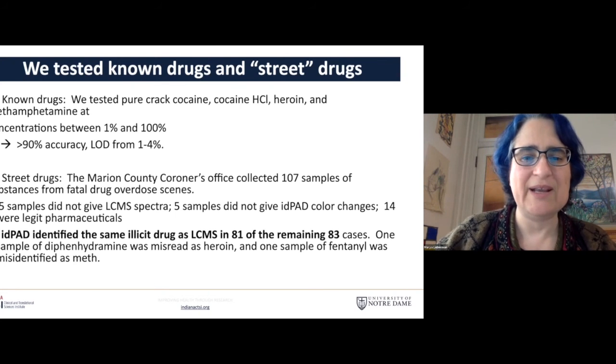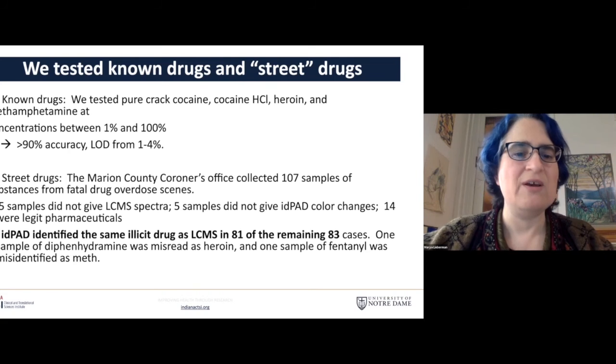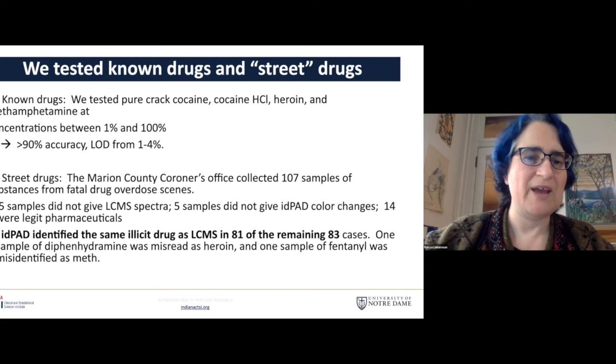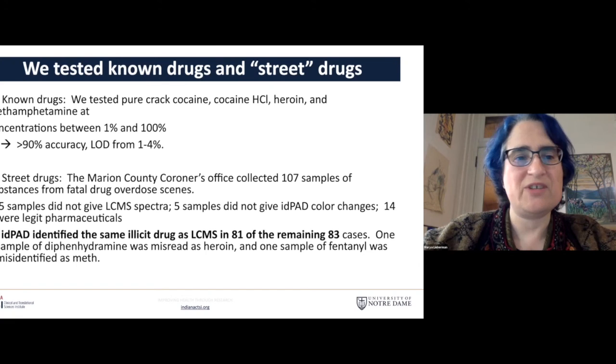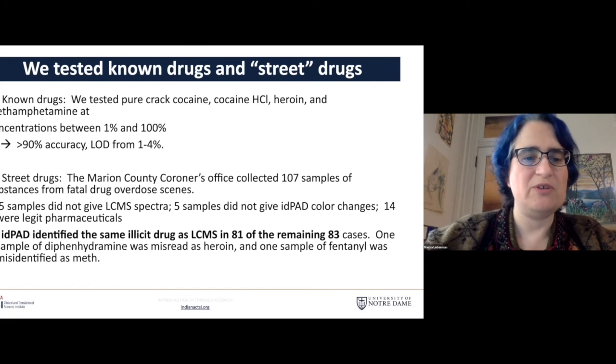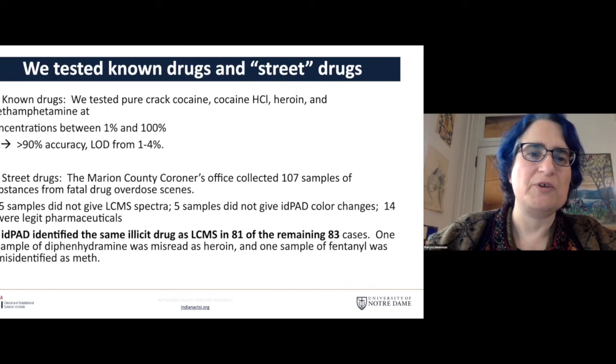In 81 out of 83 cases, we got the same result from the ID pad that we got from LCMS. LCMS can detect trace components, which the ID pad can't. But in the case of a drug overdose, we're usually looking for a major component.